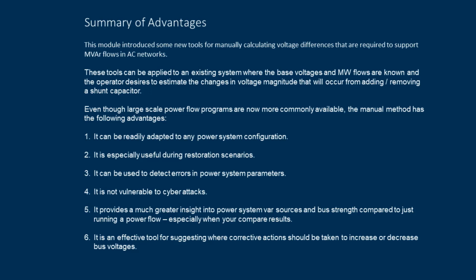So even though large-scale power flow programs are more commonly available, a manual tool really still has advantages. It can be adapted to any power system configuration. It is especially useful during restoration scenarios. Conventional tools like state estimator and contingency analysis are often overloaded and will not converge under such situations. It can be used to detect errors in power system parameters. Clearly, it's not vulnerable to cyber attacks because basically you're running with maps of your system and an Excel calculator.